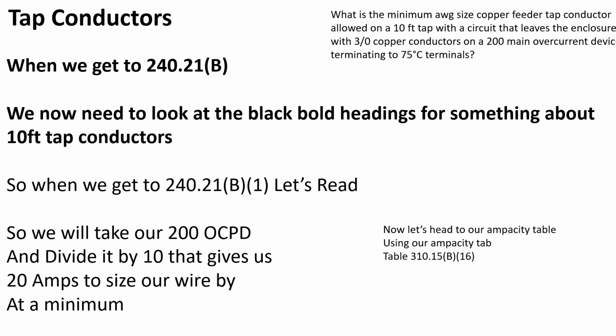Now, we are going to head to our ampacity table using our ampacity tab, and that is Table 310.15(B)(16). Go ahead and flip there now. So we use our ampacity tab. We're going to flip to page 150. We're dealing with copper conductors, and we are going to go to the 75 degree C column. And we're going to go down and size based off of our amperage, and that is going to be a 14 gauge wire in this case. So for this tap conductor, you are allowed to use a 14 gauge wire being protected on a 200 amp main breaker. So I know it sounds crazy, but this is how tap conductors work. And hold on, we're going to do another question.